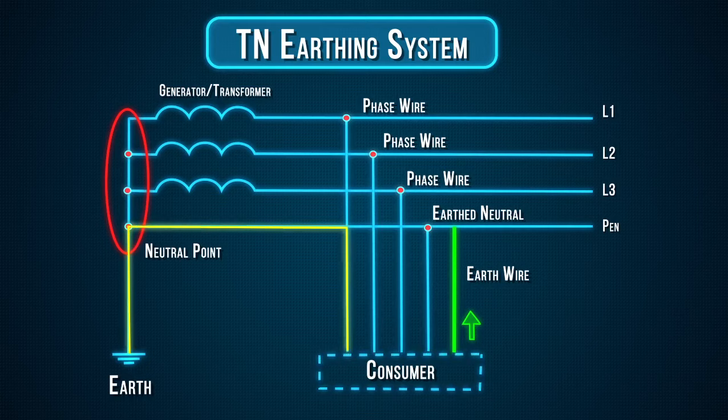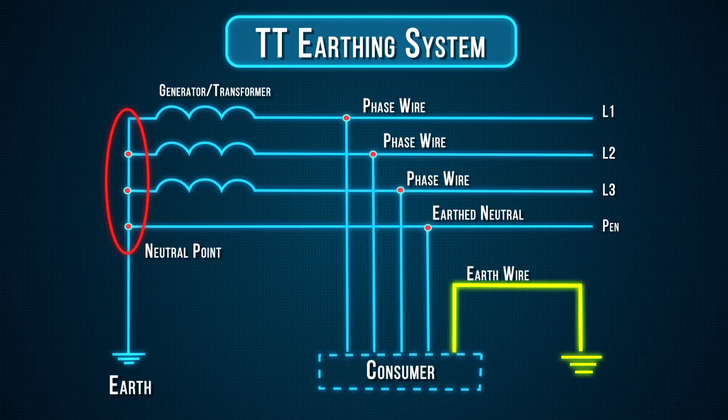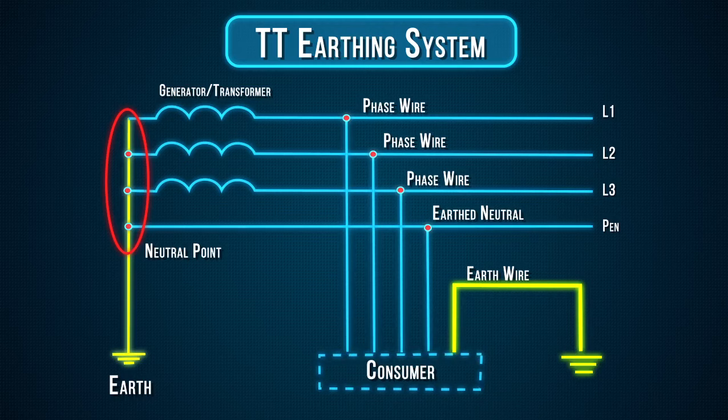In a TT earthing system, the protective earth connection for the consumer is provided by a local earth electrode, and there is another independently installed at the generator. There is no earth wire between the two. The fault loop impedance is high.